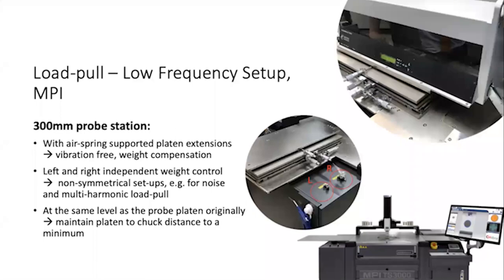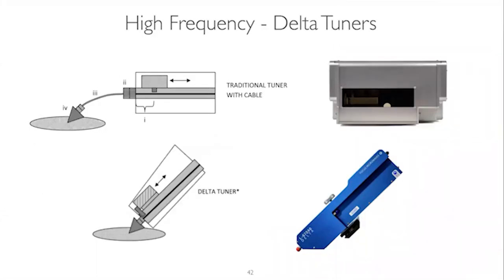Some people will say, I'll just put a cable between the tuner and the probe tip. But what happens is you're slightly changing the phase or position of that cable, and that inherently affects the impedance presented to the device. It could be slight, but when people use solutions where you actually move the tuner, the calibrations last longer and the performance is just better. That rigid airline provides definite benefits.